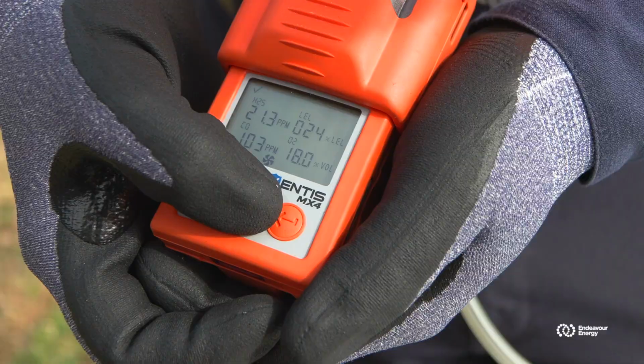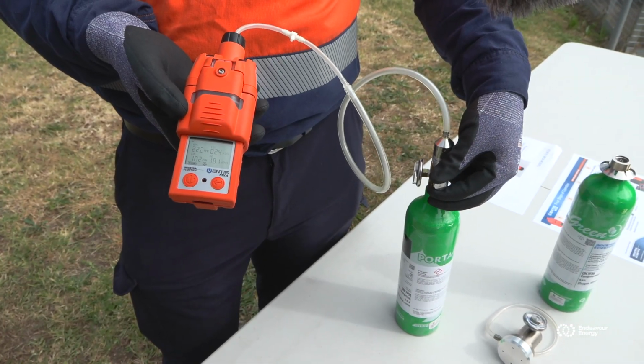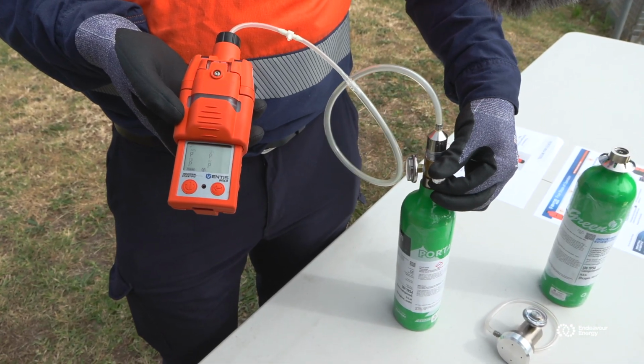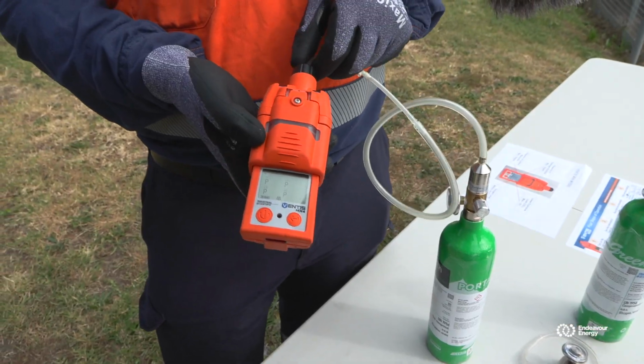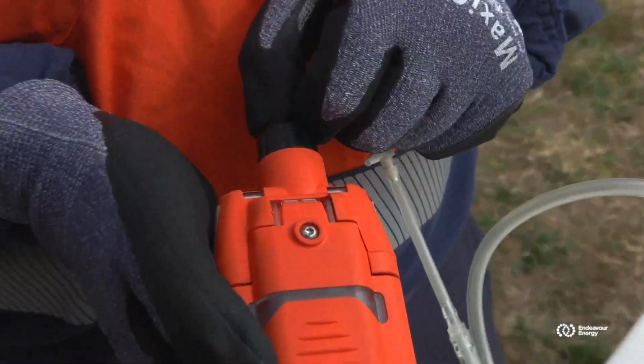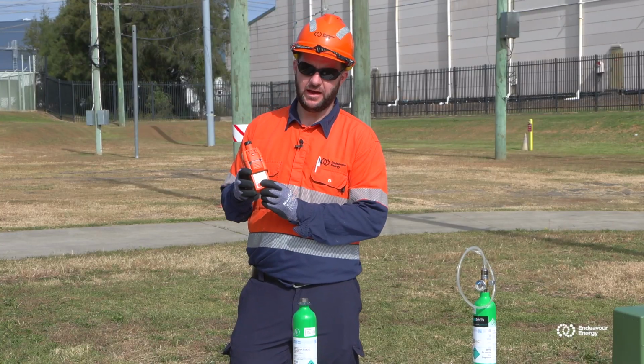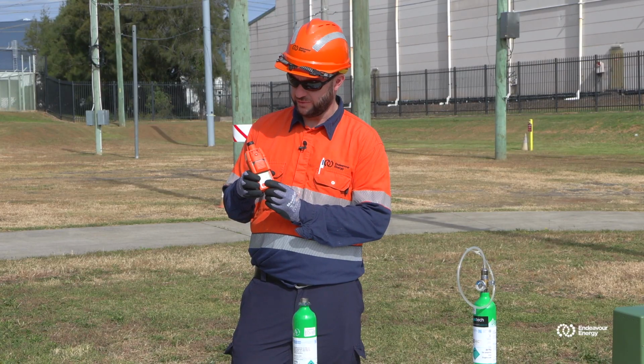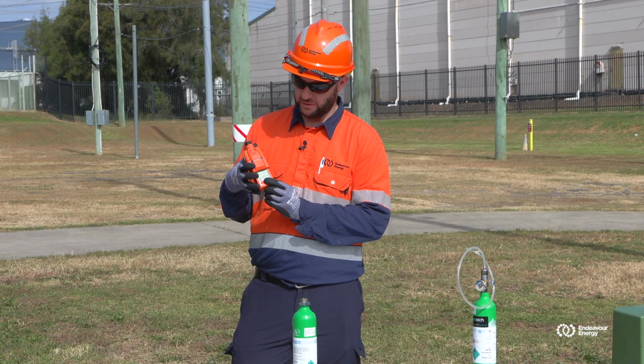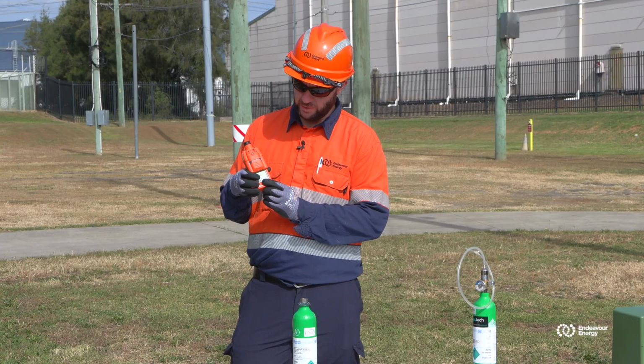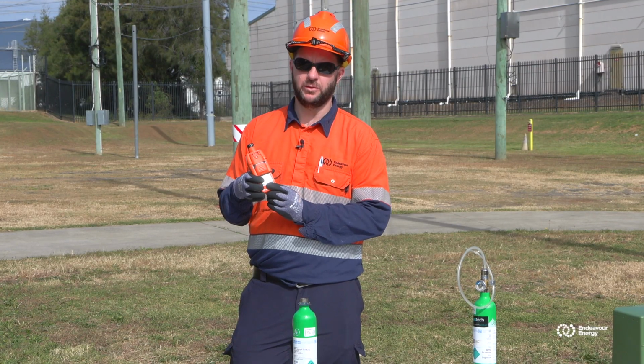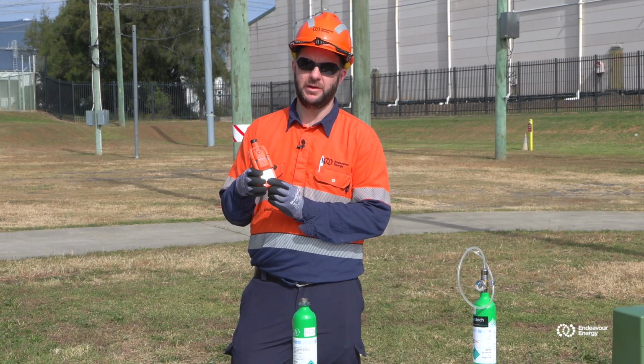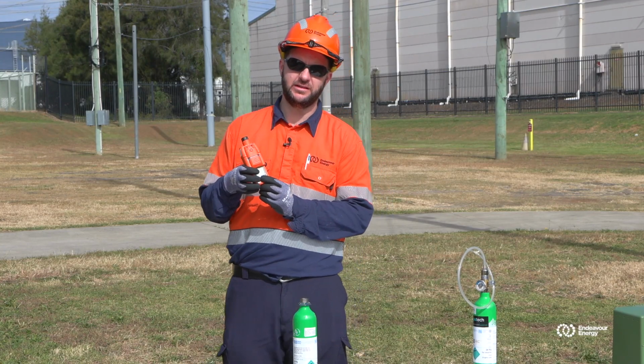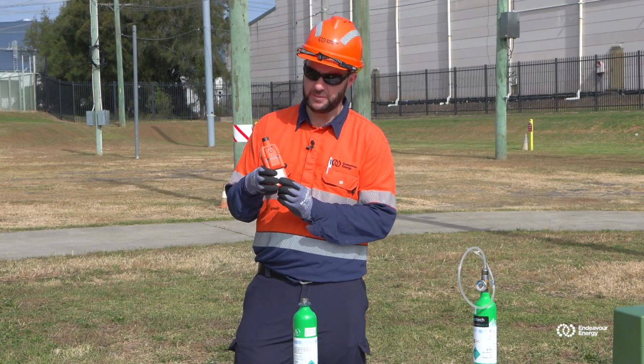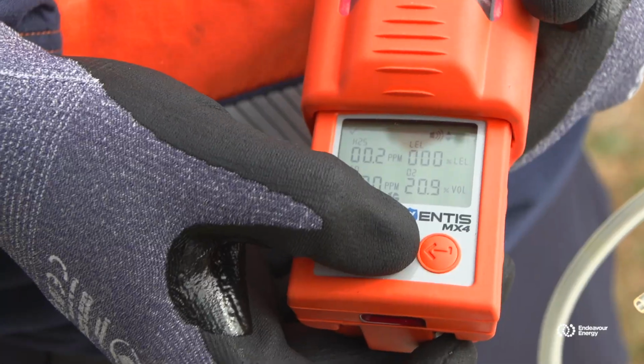What we're going to do now is turn off the valve on the test cylinder and disconnect the hose. Sometimes we may have alarms still going off because we need to acknowledge the alarm, which we'll do by pressing and holding the button. As well as that, you may still have small amounts of trace gases inside the gas detector, which keeps setting off the alarm. So we may have to wait a short amount of time for those to clear.